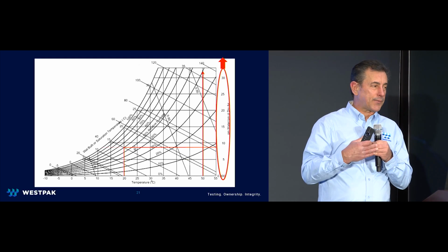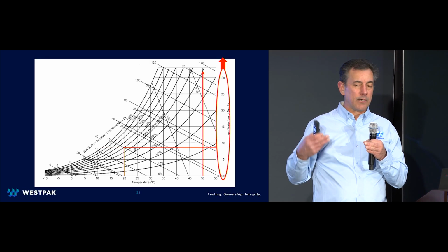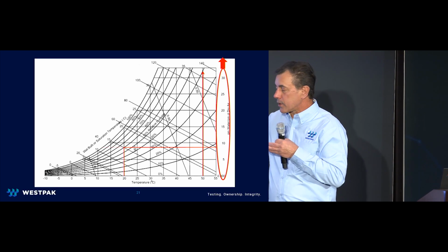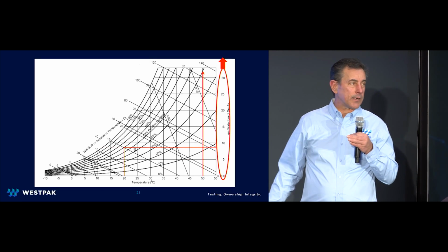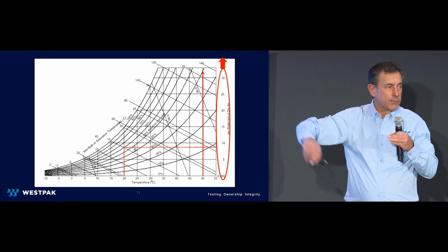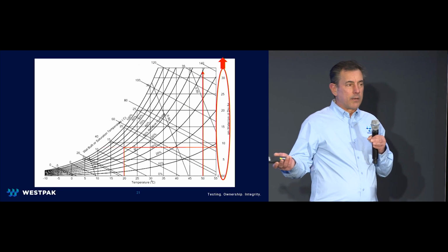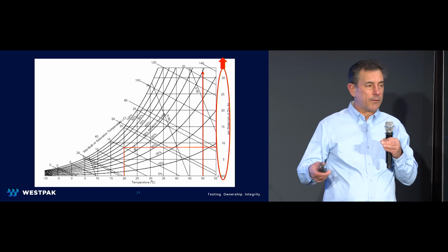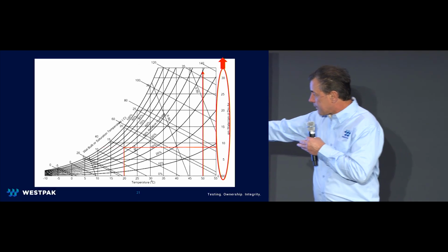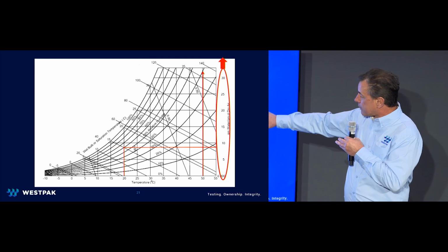So we go plus 55, that's the most popular condition that we offer for accelerated aging. And we're going to add 50% relative humidity. Again, that's a lot of moisture, but that's what we're going to offer. Some of our other clients are considering other levels, like 20% humidity. Even at 20%, that's still a lot of moisture. That would be right over here.